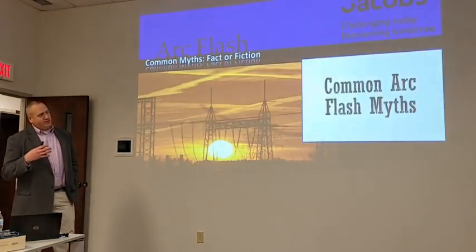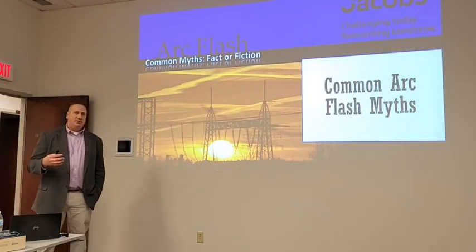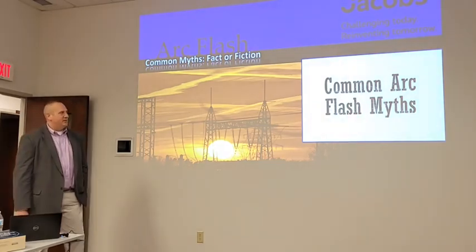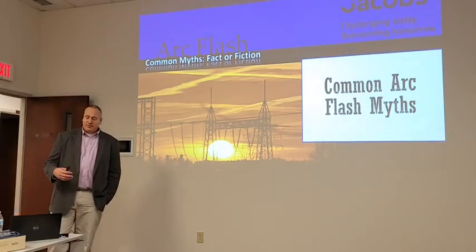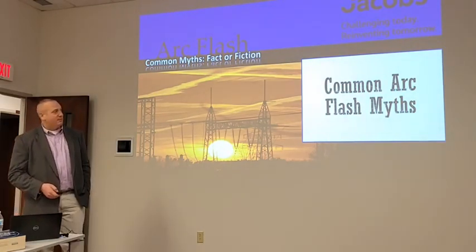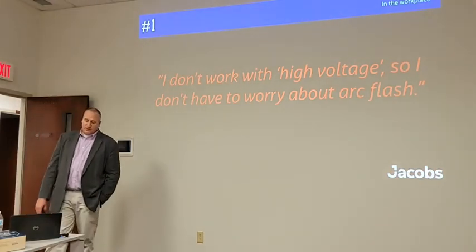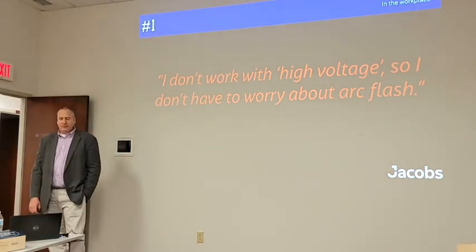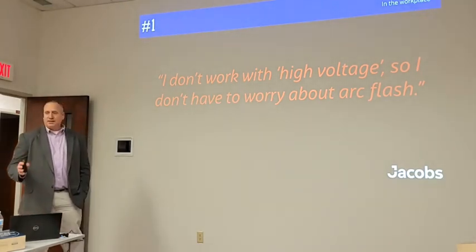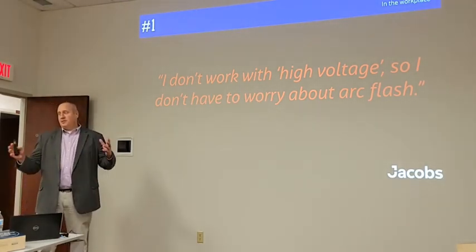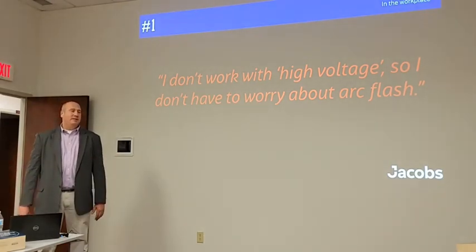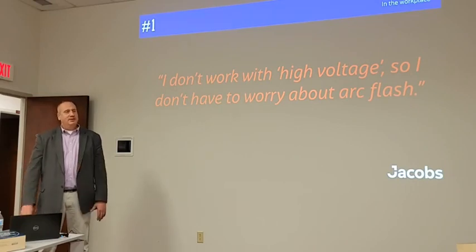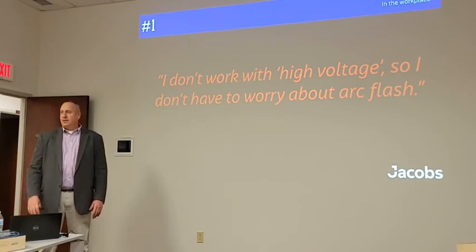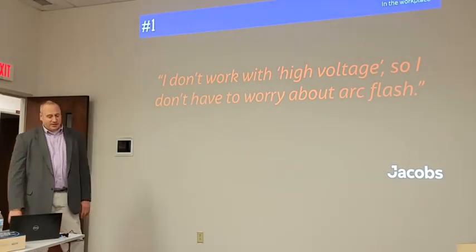So again, these are a collection of myths, if you will, or scenarios in a lot of cases that I've run into as I go evaluate facilities, and I try to clarify the truth behind the scenario and what the approach should be. One of the scenarios is, I don't work with high voltage, so I don't have to worry about arc flash. I hear that all the time, especially from a controls-based audience: all I do is work with PLCs, or anything over 48 volts or 24 volts I don't mess with, so I don't have to worry about arc flash.